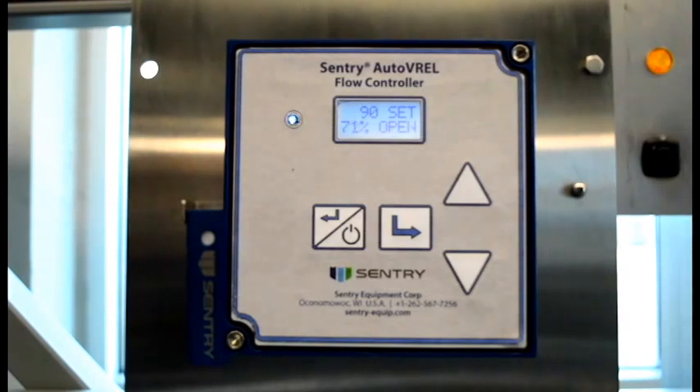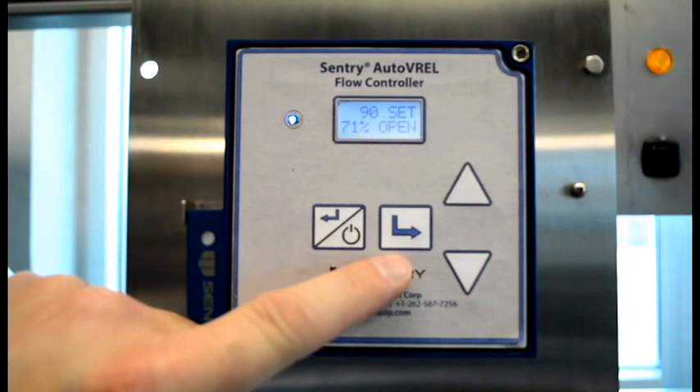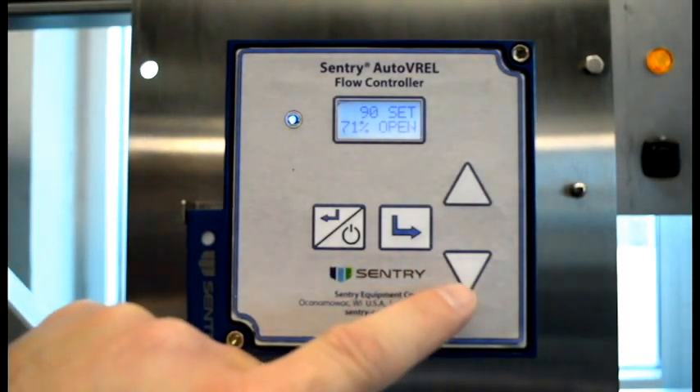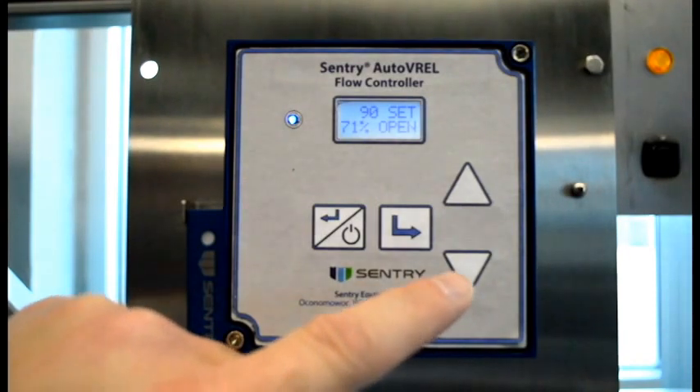While operating, you can scroll through the operator screens by depressing the Enter key. If you want to adjust the flow set point, the set screen must be displayed. Simply use the up and down arrow to adjust flow and the AutoVREL will save the new value and begin to control to that value.